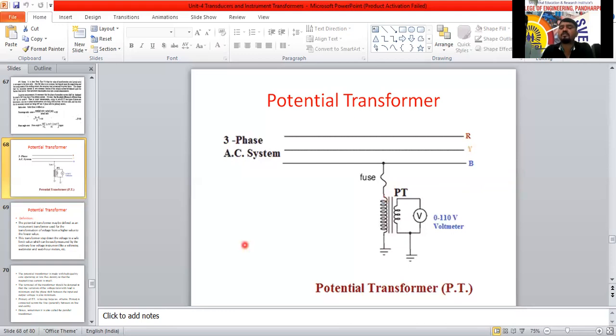The insulation cost is also reduced by dividing the primary winding into sections, which reduces the insulation needed between the layers. By doing this, we can reduce the insulation grade.